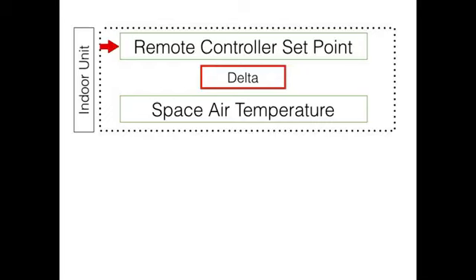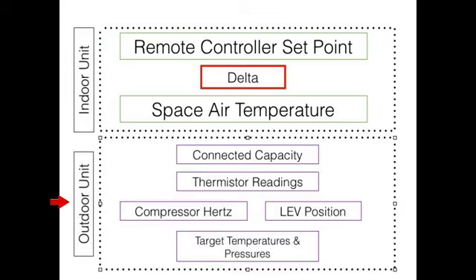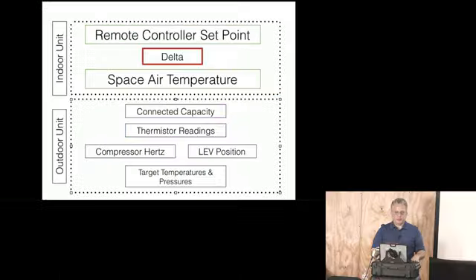So you set the set point, and then you have the space air temperature, and that delta is what drives the system. Then you have the outdoor unit. So the outdoor unit, and this is for many multi-zones as well, single-phase multi-zones, is looking at the connected capacity, thermistor readings, the compressor hertz. Could have multiple compressors, and the LEV positions, and it's targeting temperatures and pressures that it's trying to achieve. Is that a pretty good, simplified way of understanding?